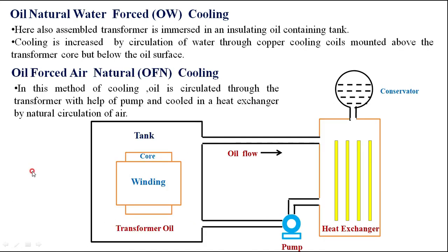The next method is oil natural water forced cooling. Here also, the assembled transformer is immersed in insulating oil in a tank. The cooling is increased by circulation of water through copper cooling coils mounted above the transformer core but below the oil surface.